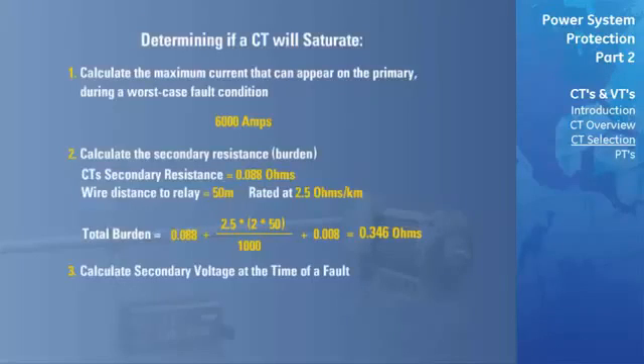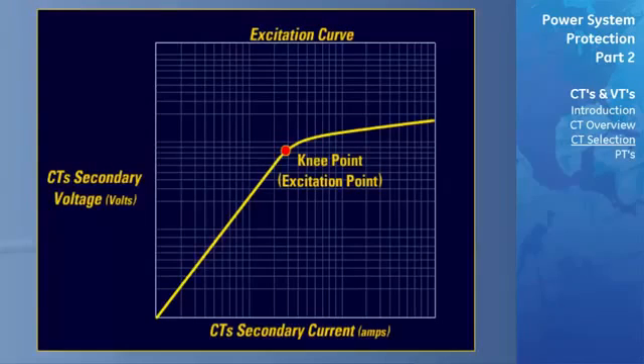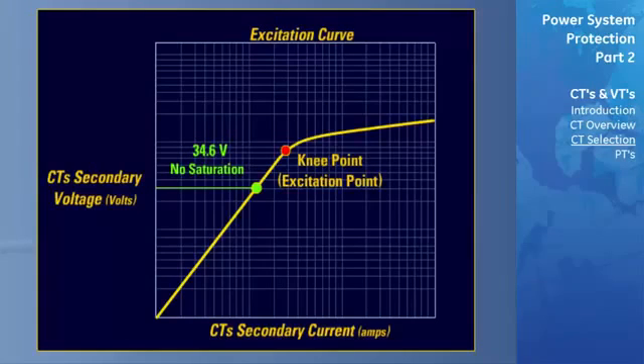Now the secondary voltage at the time of a worst-case fault can be calculated. First, the total burden resistance of 0.346 ohms is multiplied by the maximum fault current of 6,000 amps. The result is then divided by the CT ratio of 300 to 5, concluding that the secondary voltage at the time of a worst-case fault is 34.6 volts. By plotting the 34.6 volts value on the excitation curve, we notice that it falls well below the knee point, indicating that it will not saturate under a worst-case fault condition. If the factors affecting the burden were ever to change, or a higher fault current is measured, these calculations must be repeated to ensure the CT does not saturate.